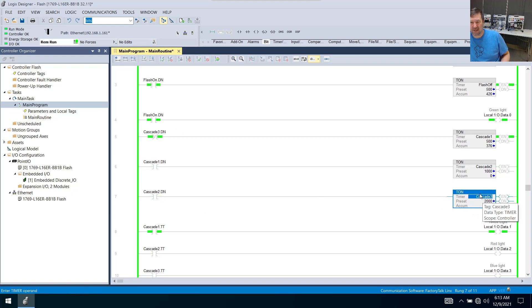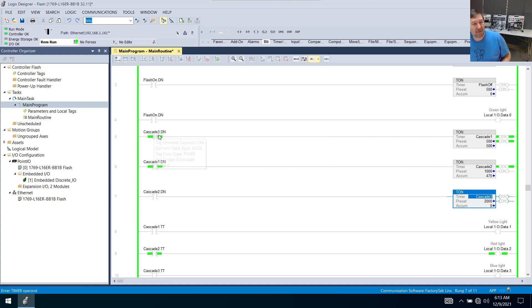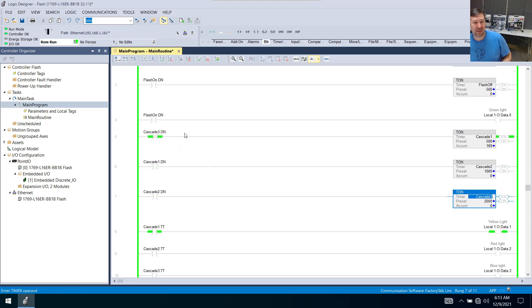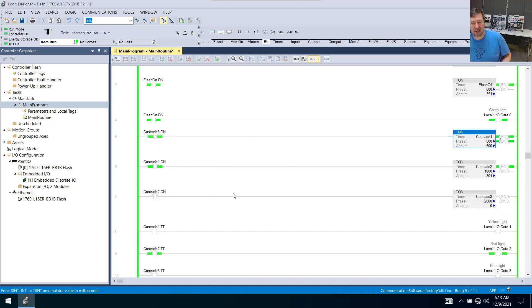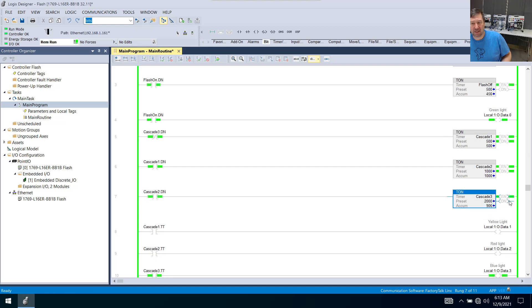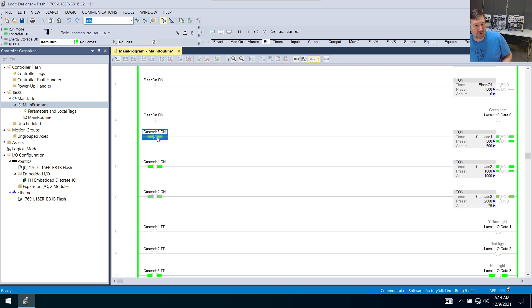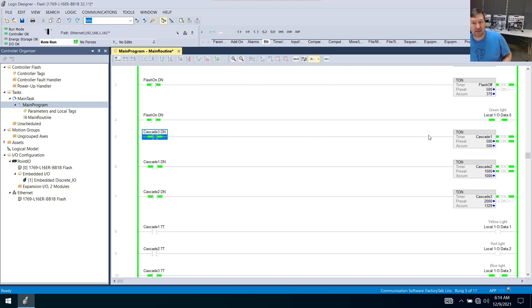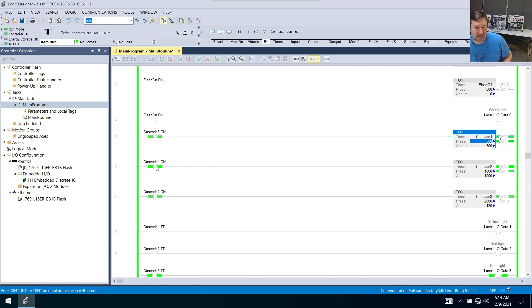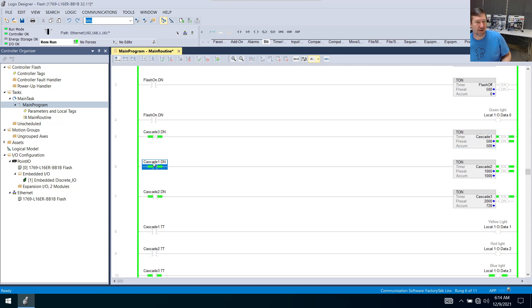Let's just pay attention to this part right here. First thing is if cascade three done is a zero, or mainly this timer is not done, it's going to start the process. And we understand, I think, how to drive it through. But let's pay attention to this part. So when our accumulated value reaches 2000 on cascade three, it's going to write a one to cascade three's done bit. This is looking for a zero in cascade three's done bit. So once it is a one, this goes false. And a false TON writes a zero to everything but its preset value, which includes the done bit that we're using right here. So now this is a zero.